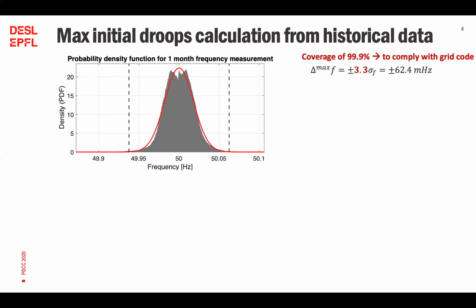This rather strict assumption is motivated by the requirement from the grid code by the National Transmission System Operator in Switzerland, Swissgrid, that requires that the quality of the supply of primary frequency control power has a maximum tolerable time of 0.1% of the tender period for which the regulating power cannot be delivered without running into penalties. That's the motivation of this 3.3 factor for the standard deviation.